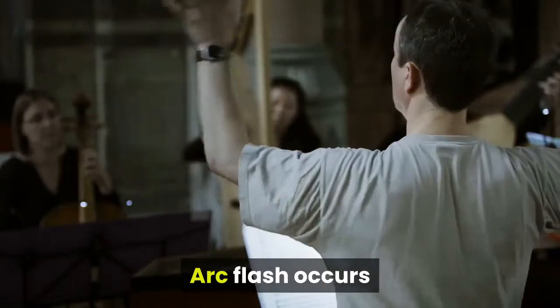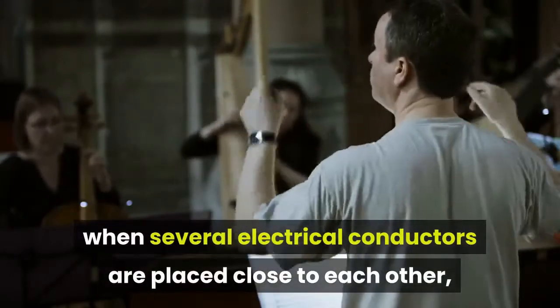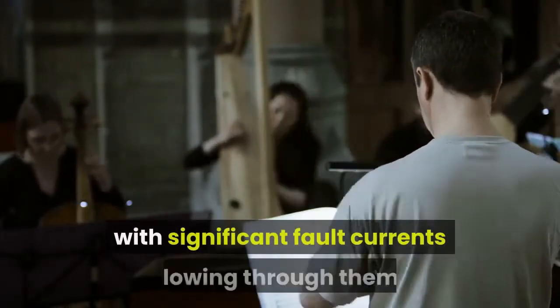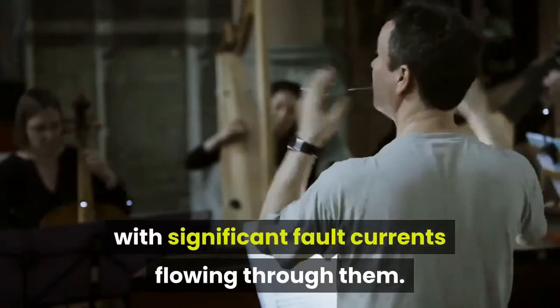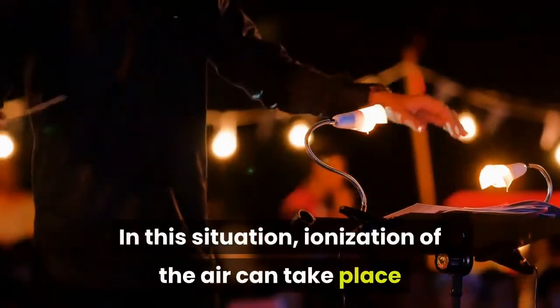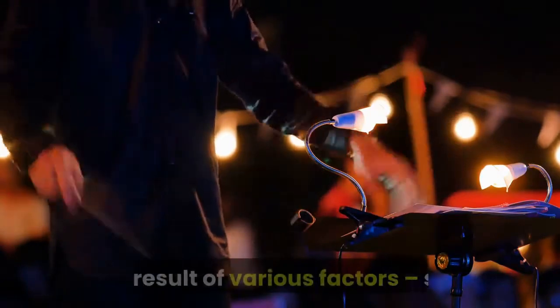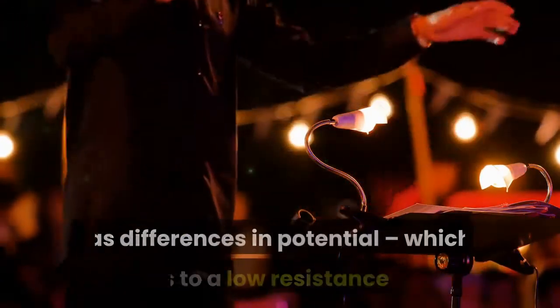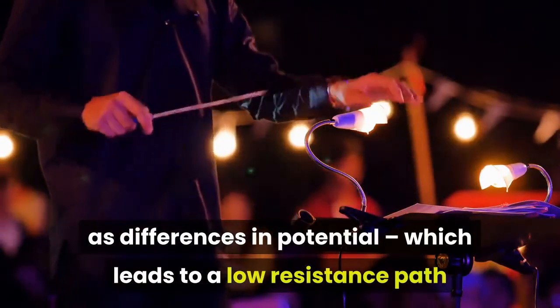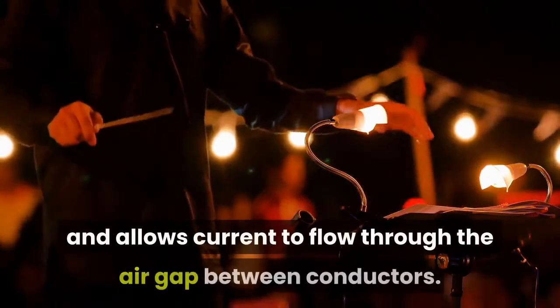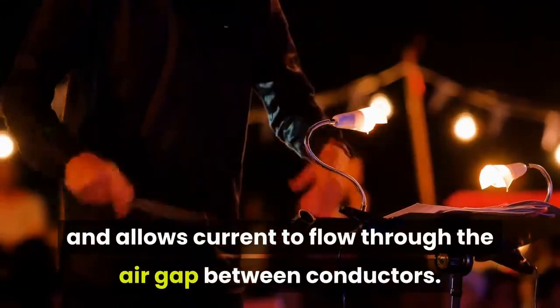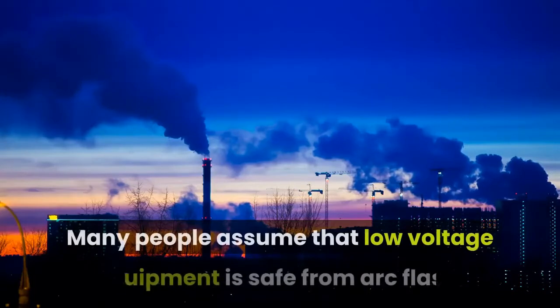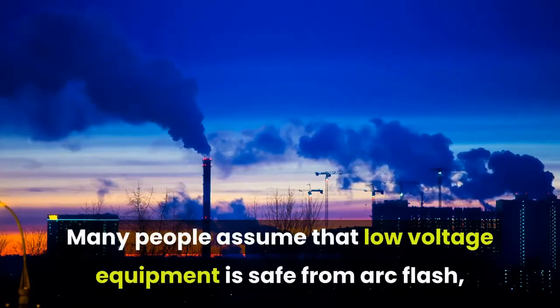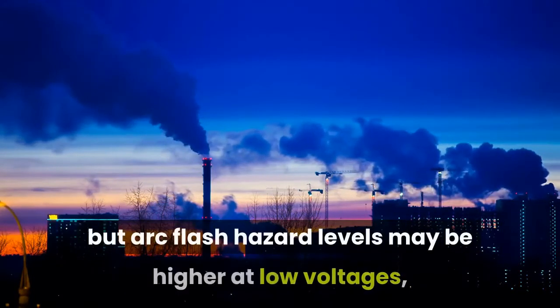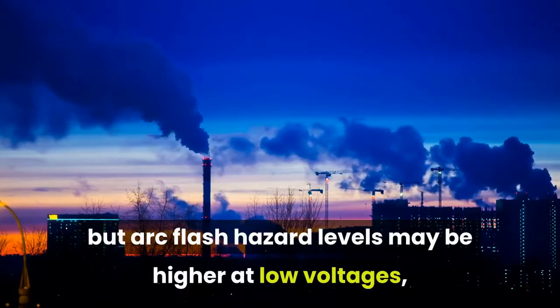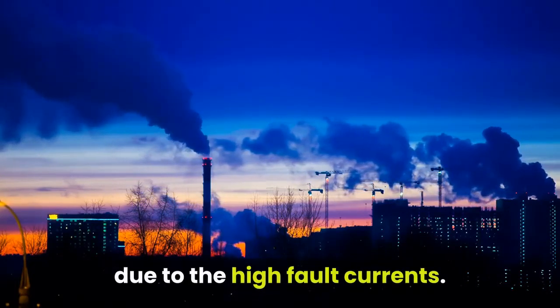Arc flash occurs when several electrical conductors are placed close to each other, with significant fault currents flowing through them. In this situation, ionization of the air can take place as a result of various factors, such as differences in potential, which leads to a low resistance path and allows current to flow through the air gap between conductors. Many people assume that low-voltage equipment is safe from arc flash, but arc flash hazard levels may be higher at low voltages, due to the high fault currents.